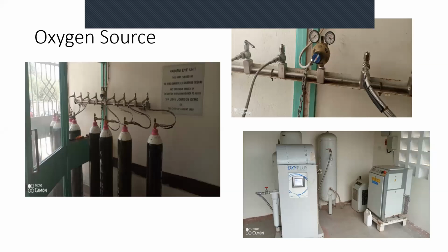In preparation for the 4th wave, we have a small oxygen processing plant set up next to the isolation. That's the 3rd picture at the bottom. At the top, you have a regulator, which you can use to check the pressures of oxygen within the pipe system.